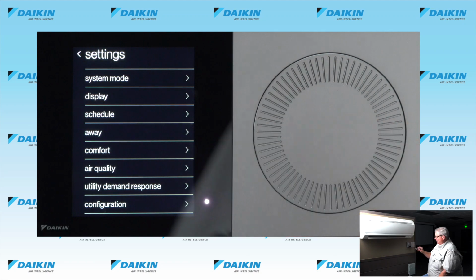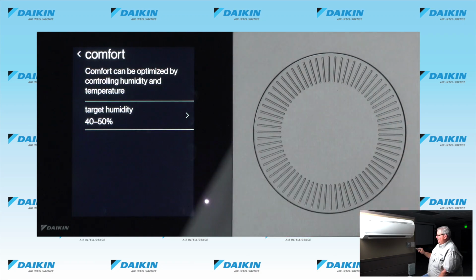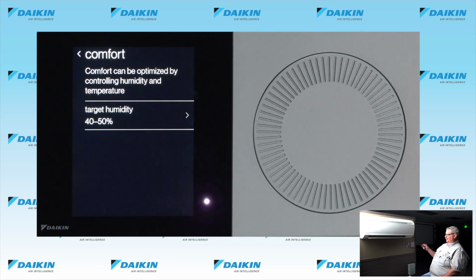Our comfort mode. This will give us our target humidity. So it'll tell us what our range are if we are doing humidification. There again, that is a feature that is not readily available for the mini splits. That is for the unitary equipment. Even though it does have a humidity sensor in here, and it does ask what is your target humidity.